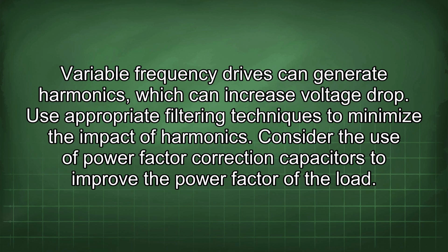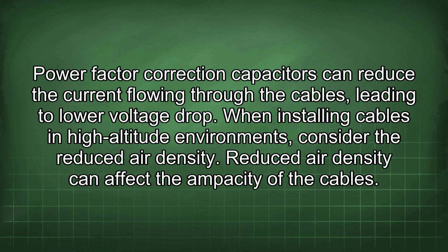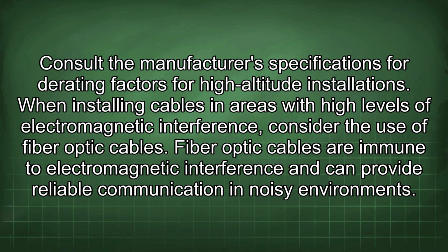Consider the use of power factor correction capacitors to improve the power factor of the load. Power factor correction capacitors can reduce the current flowing through the cables, leading to lower voltage drop. When installing cables in high-altitude environments, consider the reduced air density. Reduced air density can affect the ampacity of the cables. Consult the manufacturer's specifications for derating factors for high-altitude installations.